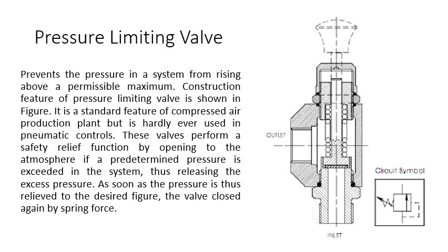The pressure limiting valve prevents pressure in a system from rising above a permissible maximum. The permissible maximum is set by the person who specifies what pressure is required. It will prevent the pressure from rising above that certain value. The construction and features of the limiting valve are shown in the figure. It is a standard feature of compressed air production plants but is hardly ever used in pneumatic controls. These valves perform a safety relief function by opening to the atmosphere if the predetermined pressure is exceeded.